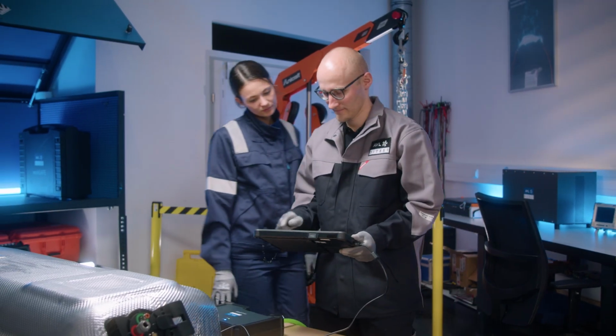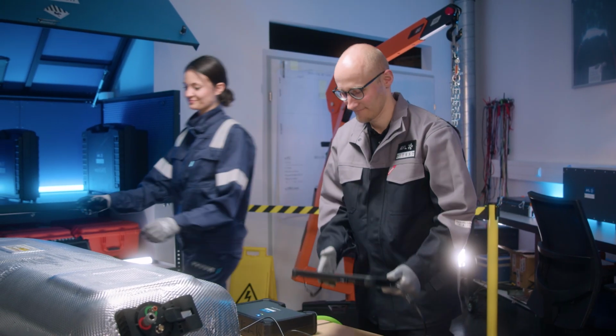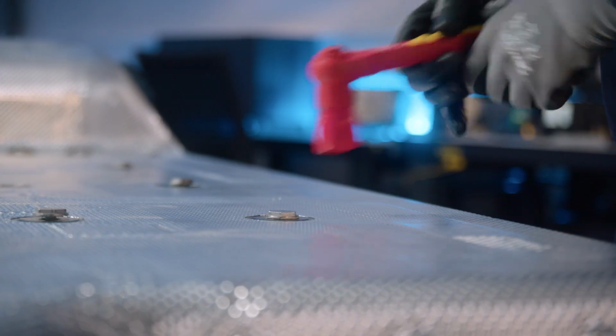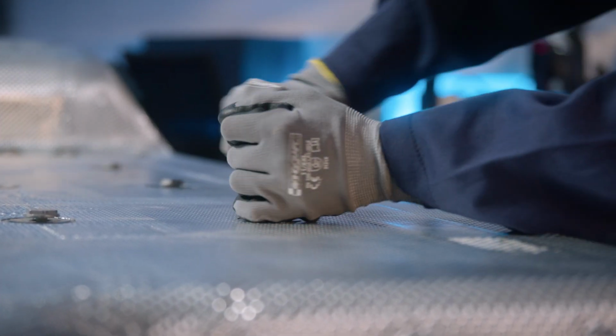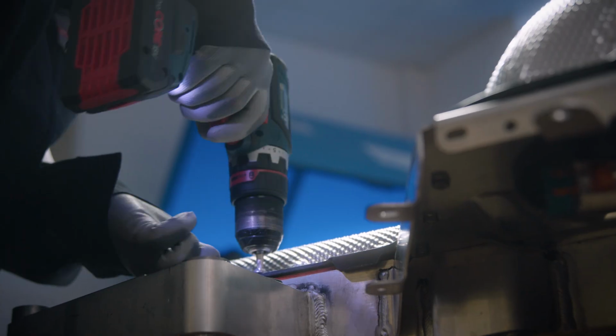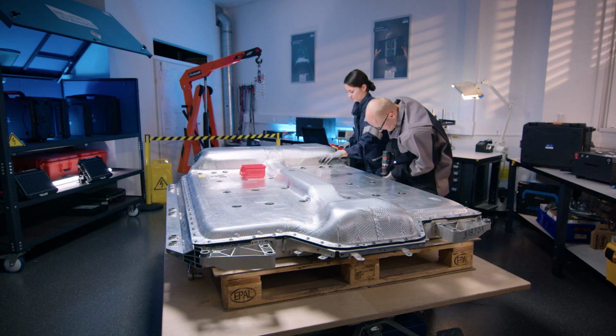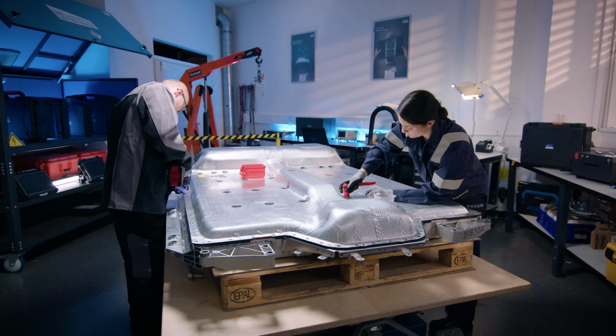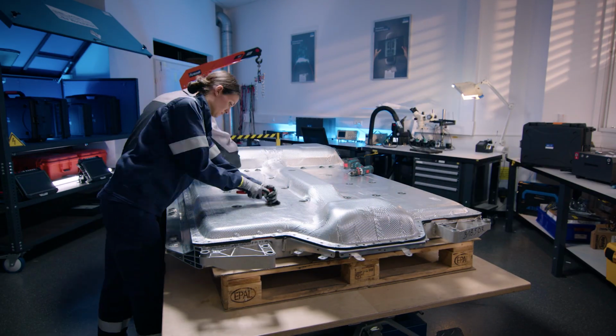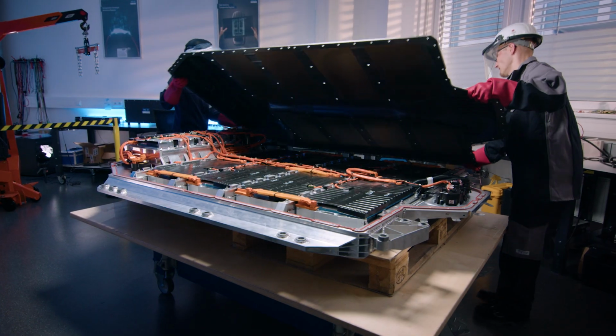After the initial leak test, you can open and inspect the battery to identify any issues, such as corrosion, dirt, loose connections, and other obvious damages. Extra caution must be taken when working on the open battery. Due to the high voltage, the appropriate safety equipment and clothing is crucial and specific training is needed.